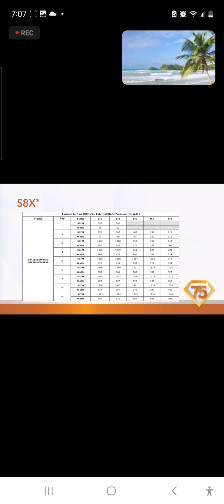This would be an 80%, the S8X2 60,000 with a 4-ton. And if you'll notice, we have different speed taps here. Some of this is going to be different. We have a different heat exchanger, so we have different resistance across it for the fan to blow through. This changes things. So here, a speed tap 5, this is still a 4-ton blower. It's actually the same motor. You'll notice that we have different CFM. So here at speed tap 5 at 0.1 static, you're at 1362. We move up almost 70 CFM. And at a high 0.9 static, we're at 946, so over 50 CFM slower. So we have 50 CFM slower on the high static, and almost 70 CFM higher on the low static. Just because it's a 4-ton blower doesn't mean you're going to have the exact same CFM. So it is important that you are checking your service facts and checking what your static pressure actually is.